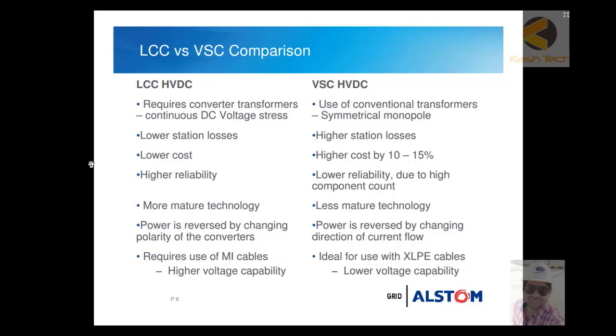In LCC HVDC, power is reversed by changing the polarity of the converter voltages, meaning you must completely change polarities from station A to B. In VSC HVDC, power flow direction is reversed by changing the direction of current flow — no need to change the voltage polarity. LCC HVDC requires the use of MI cables with higher voltage capability, whereas VSC HVDC is ideal for use with XLPE cables but has lower voltage capability. This concludes the basic comparison between LCC and VSC converters.